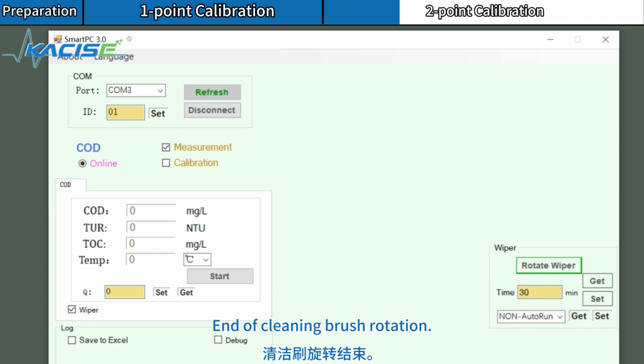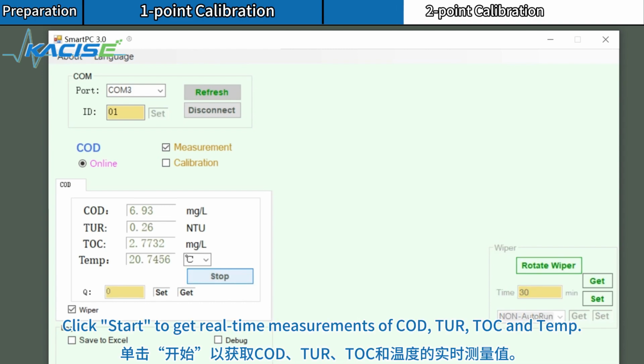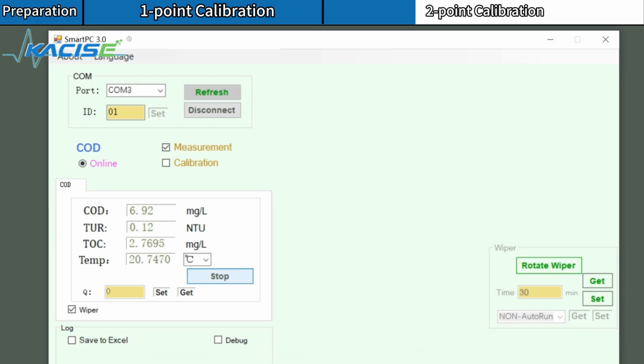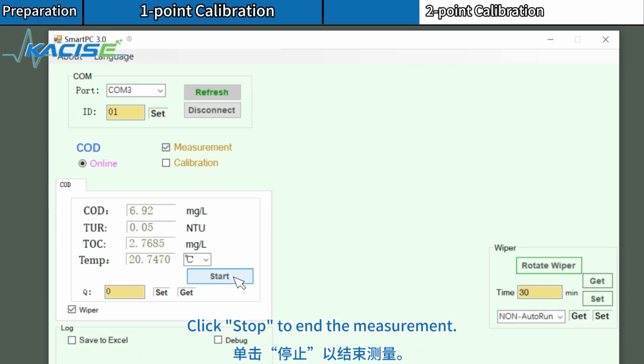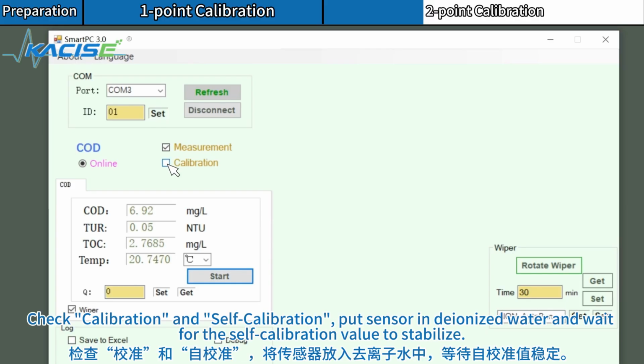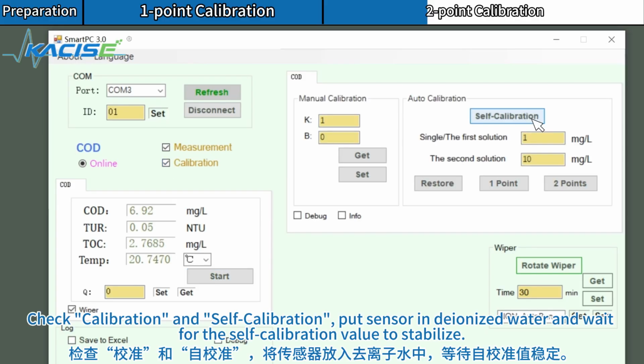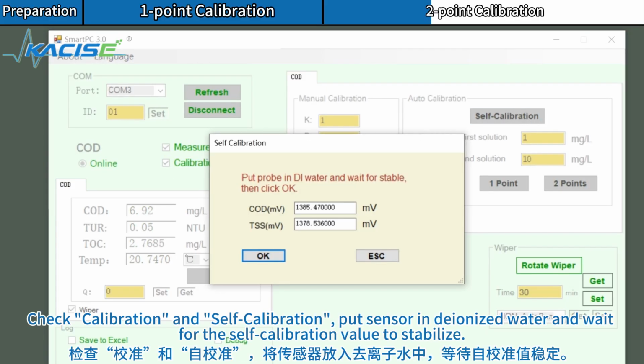End of cleaning brush rotation. Click Start to get real-time measurements of COD, TUR, TOC, and temp. Click Stop to end the measurement. Check Calibration and Self-calibration. Put sensor in deionized water and wait for the self-calibration value to stabilize.